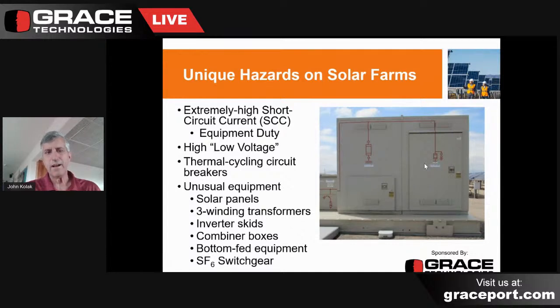But at the moment, low voltage systems is really how it's configured rather than the voltage it's actually operating at in the system. The third point, very important for solar farms, is thermal cycling, sometimes known as thermocycling of circuit breakers. What we mean by that is, with a solar farm, you get a scheduled outage every night. So the system will run at maybe 107% of nameplate during the day and something considerably less at night. So this heating and cooling of the circuit breakers really puts a premium on your maintenance of the breakers as well, because the temperature, of course, is the enemy of our insulation in the system. So when you run a system at high temperature, it breaks down more quickly.